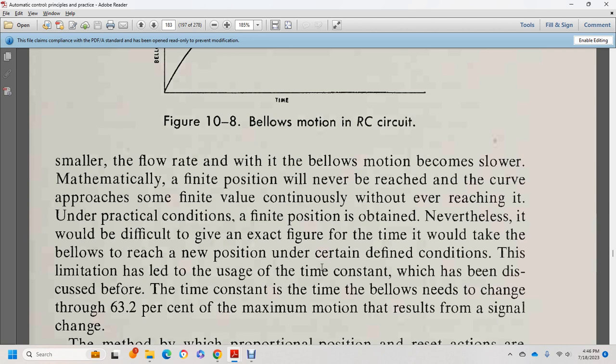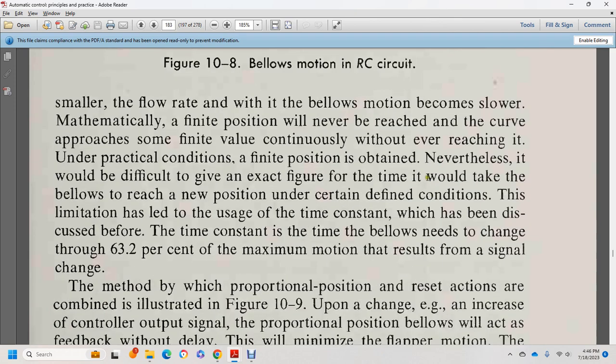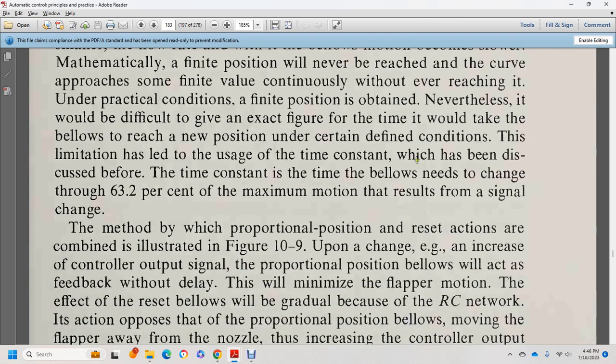Under practical conditions, a finite position is obtained, though it is difficult to give an exact figure for the time it takes the bellows to reach the new position. This limitation led to use of the time constant, which has been discussed before. The time constant is the time for the bellows to reach 63.2% of the maximum motion resulting from a single step change.